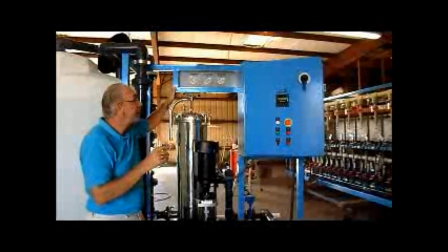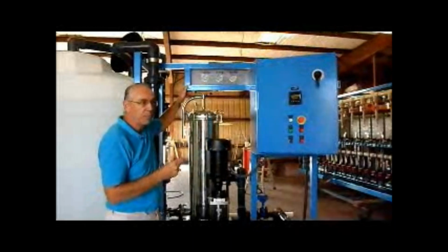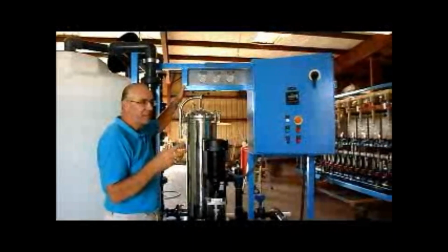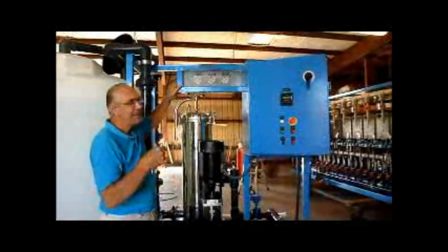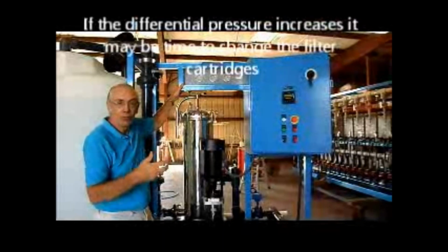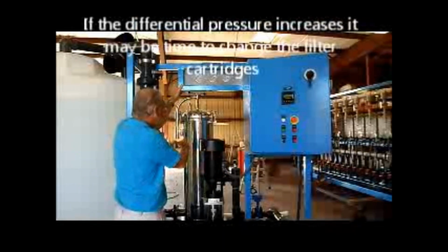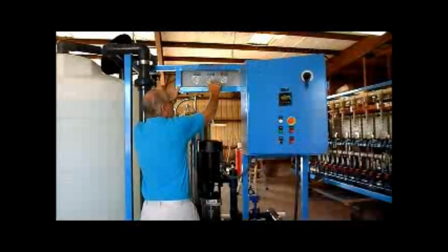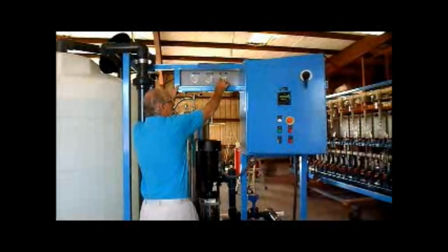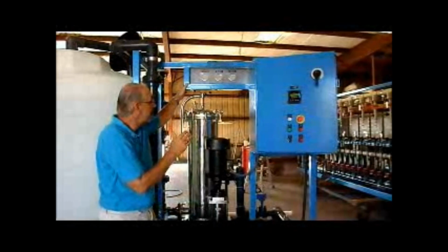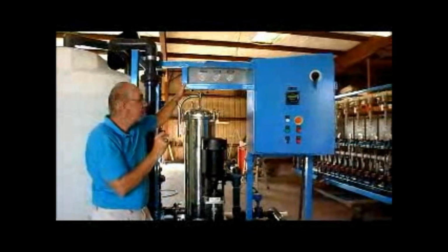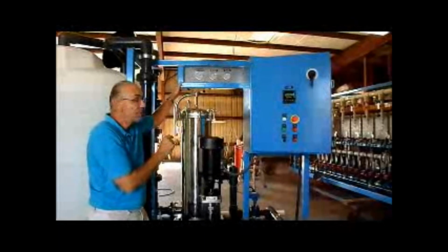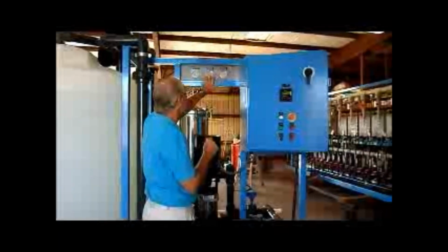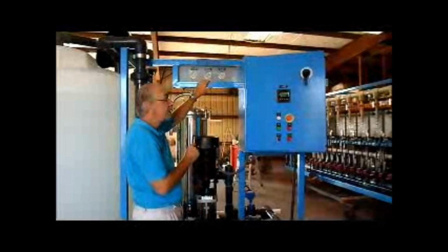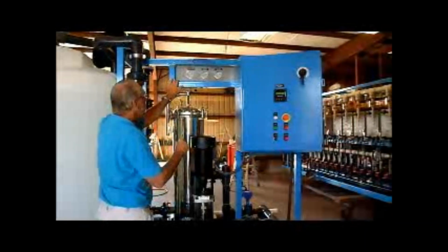It's very normal during cleaning that a lot of scale, bacteria, dirt, all kinds of things can be broken off of the membrane surface, and they'll be captured by this cartridge filter. It's very possible that over time the outlet pressure will drop, even though the inlet pressure stays relatively constant. When you start to see that differential pressure go up, you may have to change your cartridges. That's what these 2 gauges are for, just to check to see how much pressure you're losing across the cartridge.